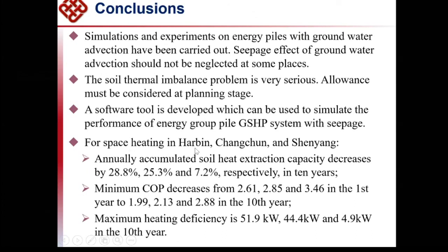For the case study in Harbin, Changchun, and Shenyang, I have told you the main result. The soil heat extraction capacity decreases, and the minimum COP decreases from Harbin to Changchun to Shenyang. Shenyang is the best. So ground coupled heat pump systems may not be a good renewable energy system for application in Harbin—very, very low COP. The maximum heating deficiency is also found to differ across the three places.